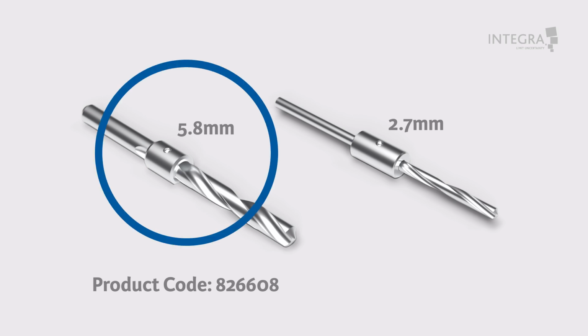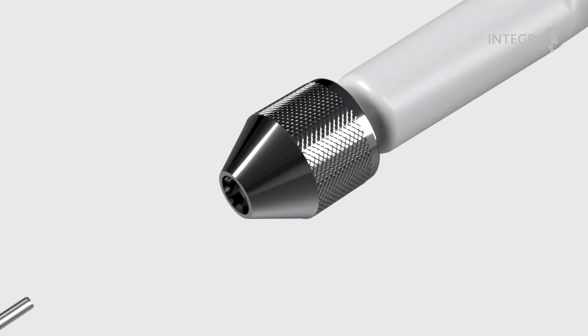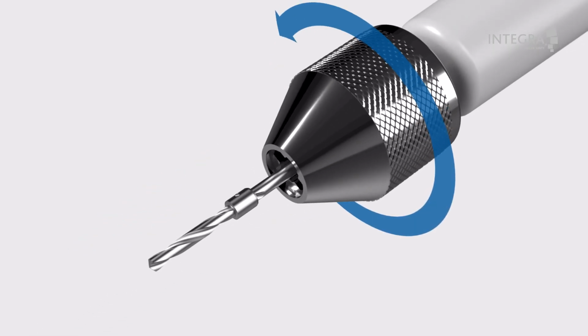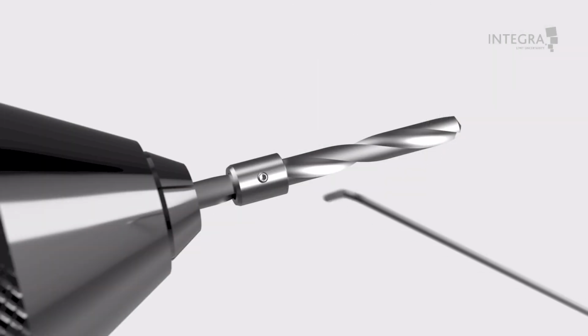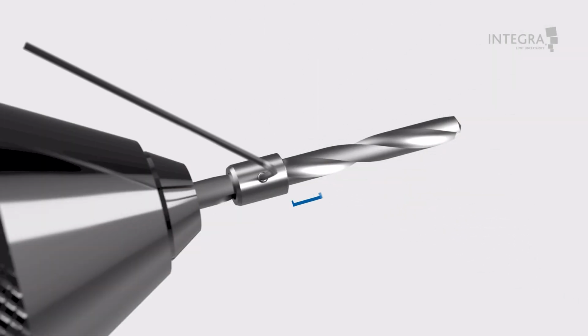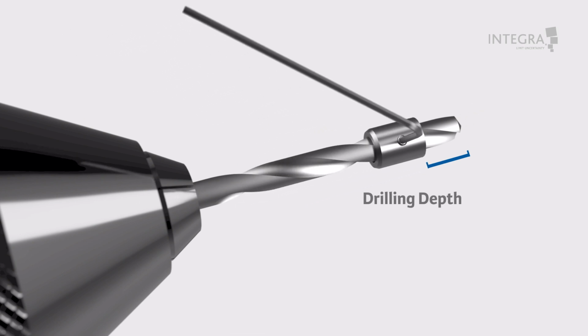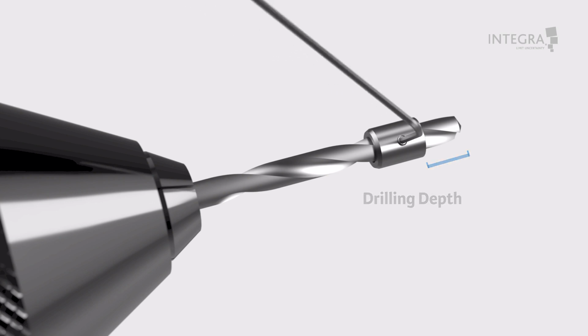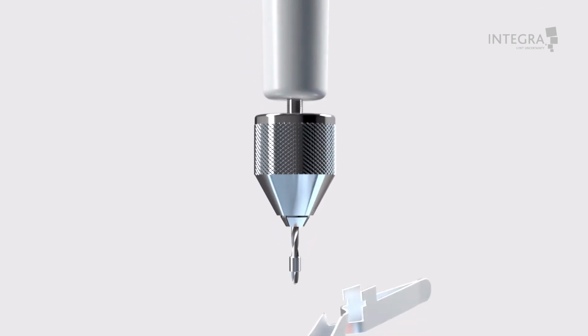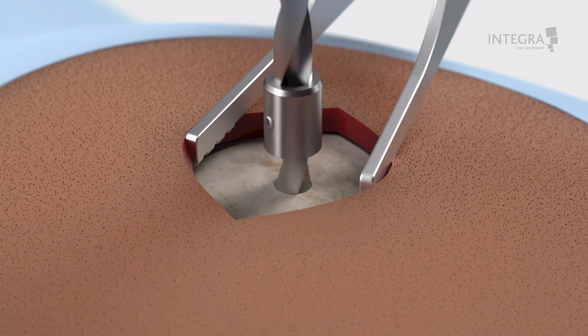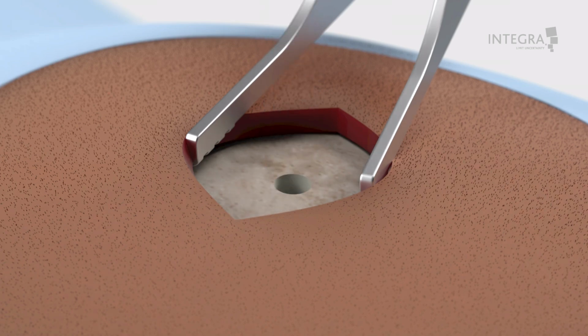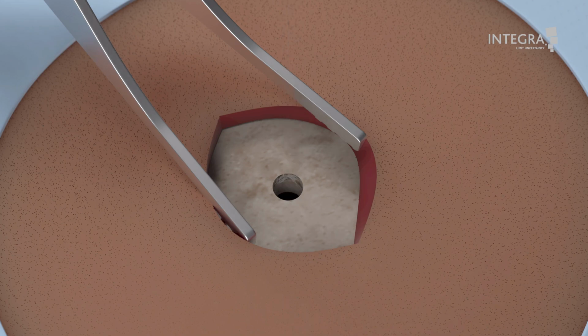Now select the 5.8 mm drill bit for subdural and intraparenchymal procedures. Place the bit into the chuck, then hold the drill handle in place and turn the chuck counterclockwise to tighten the bit. Next, loosen the drill depth guide with the appropriate hex wrench and carefully slide the drill guide towards the tip of the bit until the desired skull depth is reached. It is important to note that the drill guide will not stop the drill. It is designed only to provide the neurosurgeon with a marker for drilling depth. Finally, tighten the drill guide in place with a hex wrench and begin drilling. Open the dura with an appropriate needle or blade.